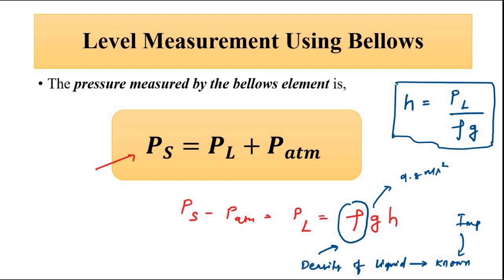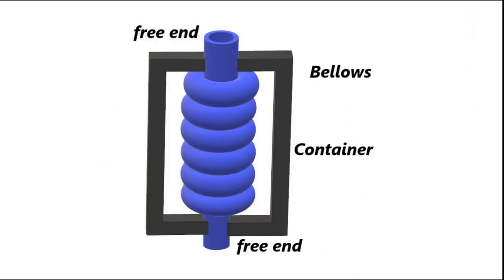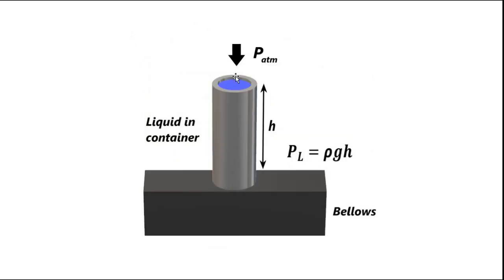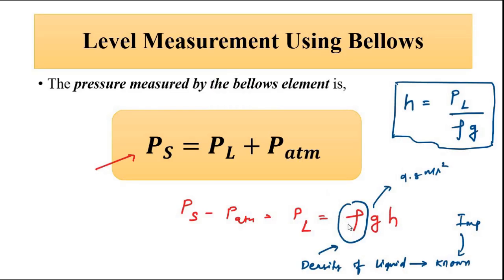So first, the bellows measure the pressure due to the liquid column and the atmospheric pressure. As the atmospheric pressure is known, we subtract it from the total pressure, which gives us the liquid column pressure, given by rho g h. Rho, the density of the liquid, should be known. Only then can we determine the level or height of the liquid h.